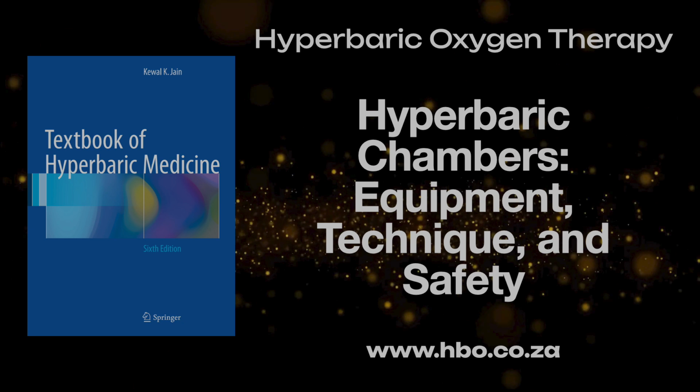Exactly. Gas supplies, chamber materials, controls, monitoring, safety devices all continue to improve, often tailored to specific chamber types, whether for treatment, training, or research. But the non-negotiables: alarms, technical monitoring, firefighting gear, pressure locks, and good patient monitoring in therapeutic chambers. A really complex blend of medicine, engineering, and safety. Thanks so much for walking us through it all. My pleasure. It's fascinating stuff.